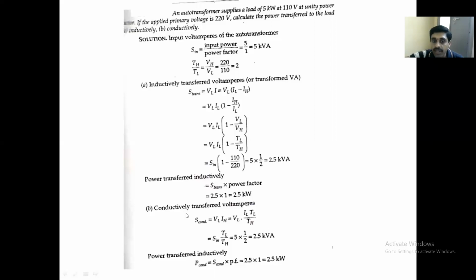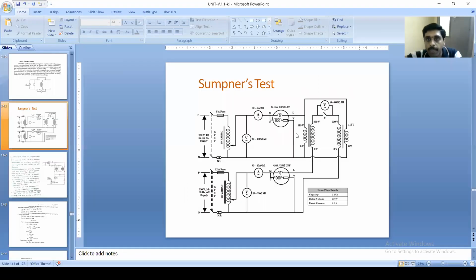That's all. What is the conductively transferred power? Our direct formula is K into input. So therefore, 5 into, what is K? 1 by A. 1 by 2. So directly you can calculate K here by taking V2 by V1. Or you can calculate A and you can do 1 by A. Anything is okay. So 5 into 1 by 2, 2.5. Therefore, what is power transfer in terms of watts? Multiply by power factor. So this is about the auto transformer discussion.